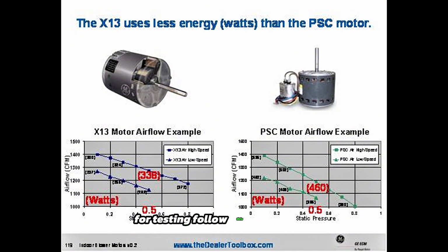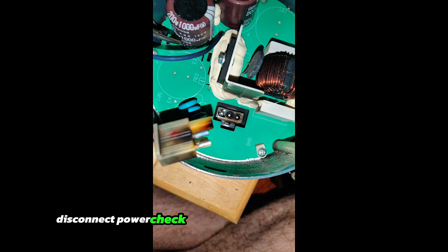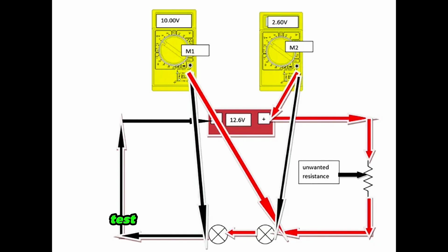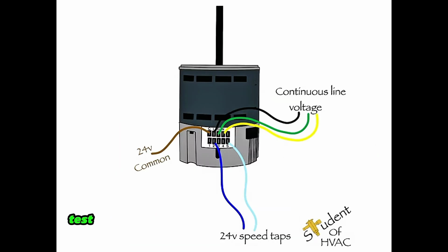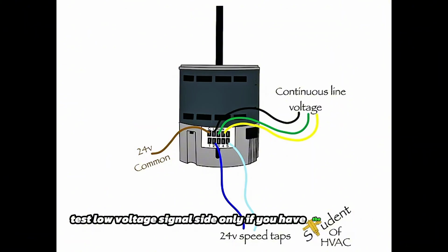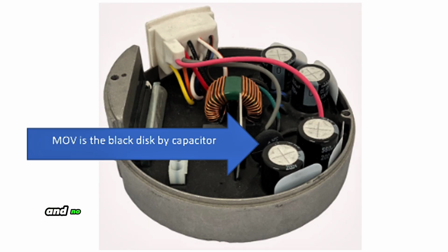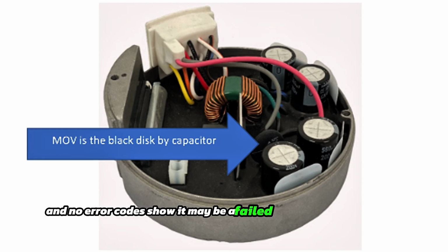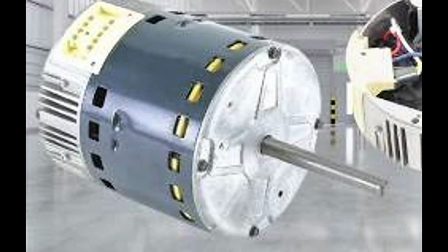For testing, follow this process. Disconnect power, check for burned smell or visible damage. Test the high voltage side with your meter. Test the low voltage signal side only if you have the specs. If the motor doesn't spin and no error codes show, it may be a failed module or the motor itself.